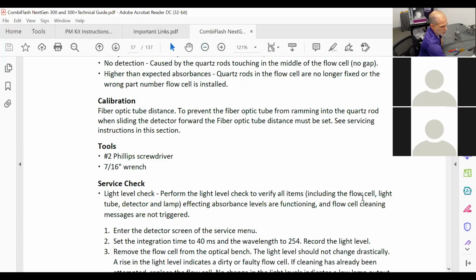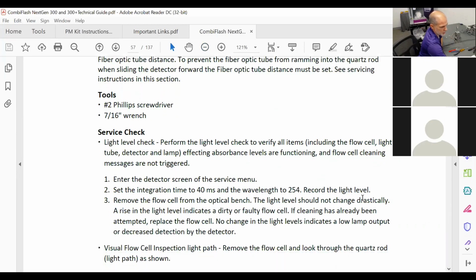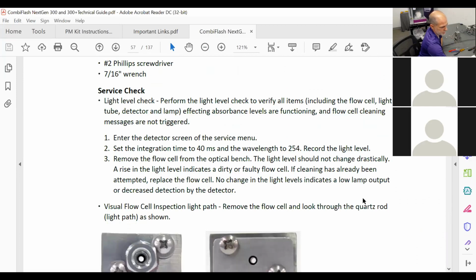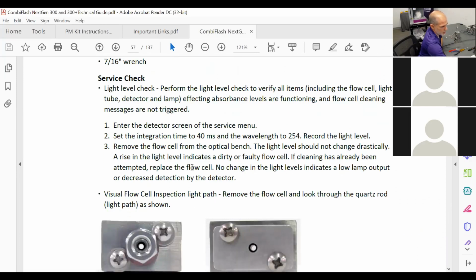And we're gonna do a light level check here. What it's telling you to do is go into the detector screen of the service menu, set the integration time to 40 milliseconds, and the wavelength to 254, and record the light level. Remove the flow cell from the optical bench. That just means take the flow cell out of the unit. And the light level should not change drastically. A rise in the light level indicates a dirty or faulty flow cell.